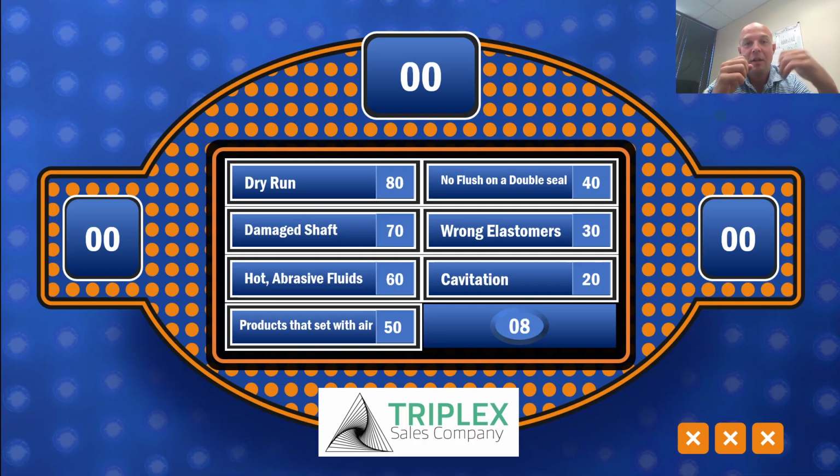In cavitation, we are releasing a lot of energy when we're compressing that fluid and it's going from a gas into a liquid. That energy has to go somewhere, and where it goes is it damages our pump, specifically our mechanical seals. So we'll start hearing things like, when pumps are cavitating, we'll hear things chatter. We're more prone to shaft deflection, premature bearing failure. All sorts of bad things start to happen when we cavitate a pump, and that is going to reduce pump seal life.